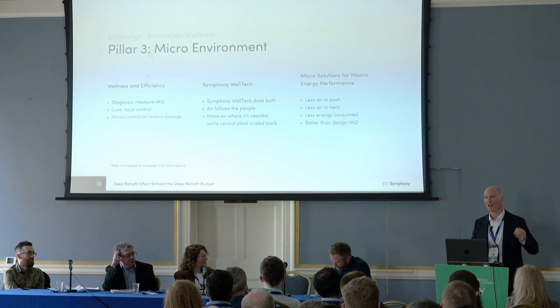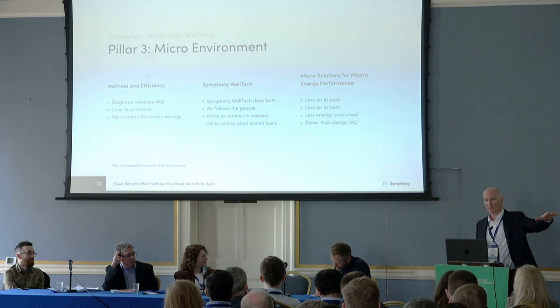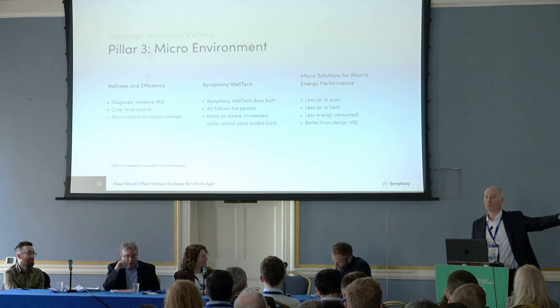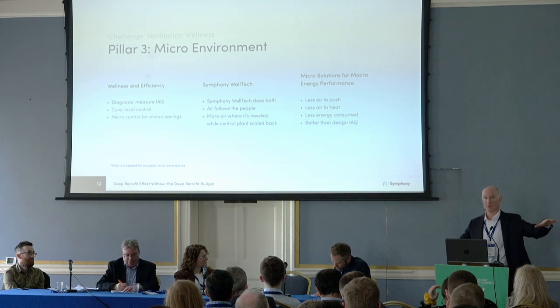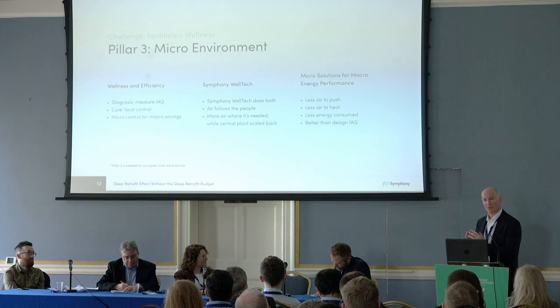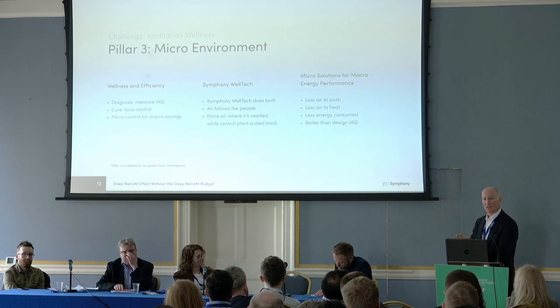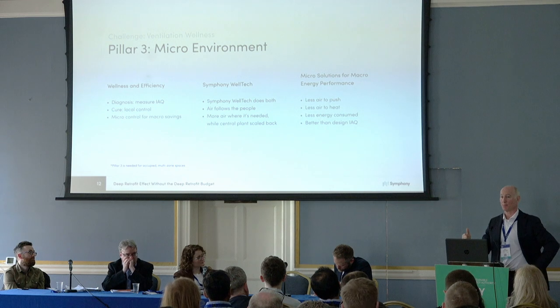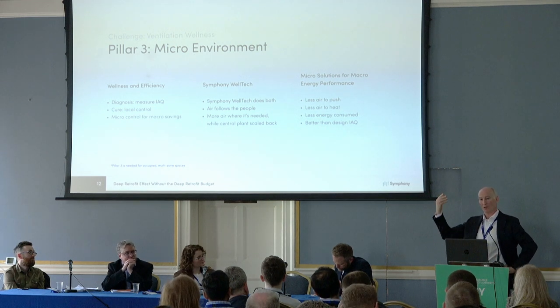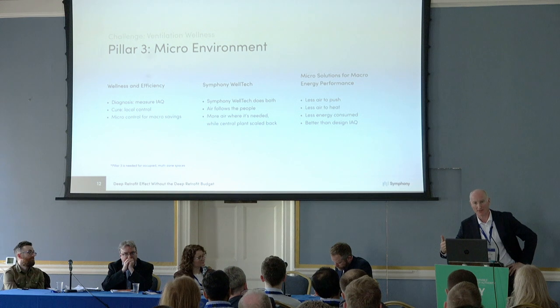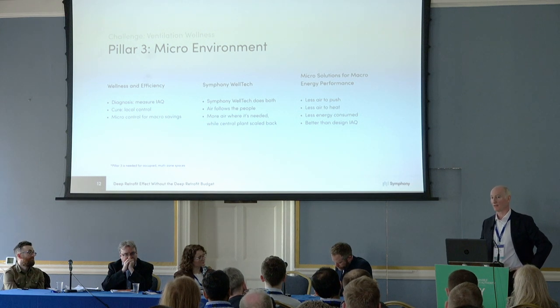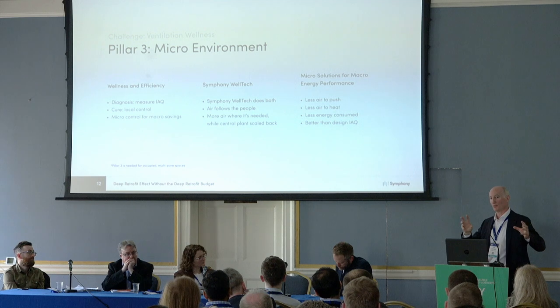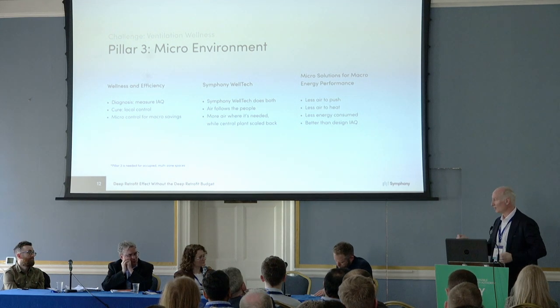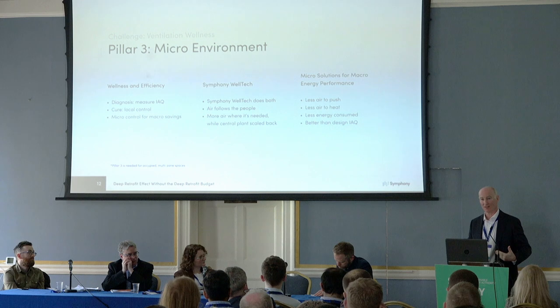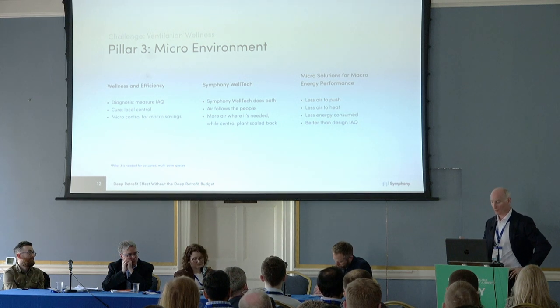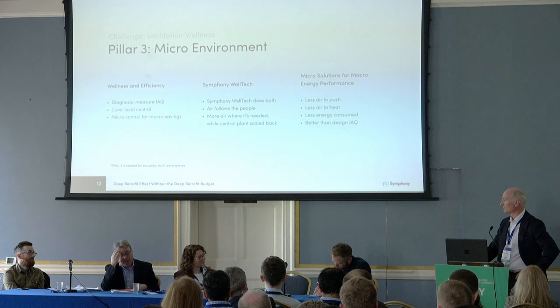If you can reduce the air supply from your central plant to a space that doesn't need it, based on dynamic measurement, you've got more capacity to drive it to areas that do need it. Take a meeting room designed for 14 people: before this process, if 18 people go in, they won't have enough air. But with this process, because you've worked out the diversification of your capacity, you can drive more air into that space and actually get better than design IAQ for that space, and for any space in the building. So it's a triple win.